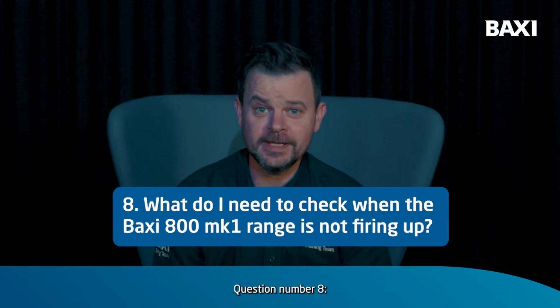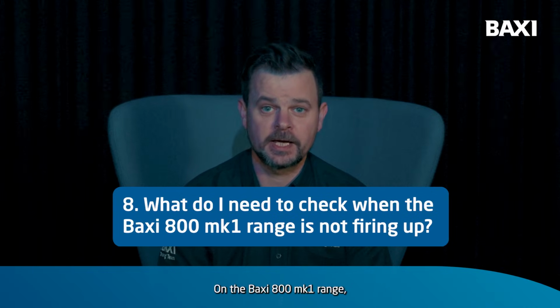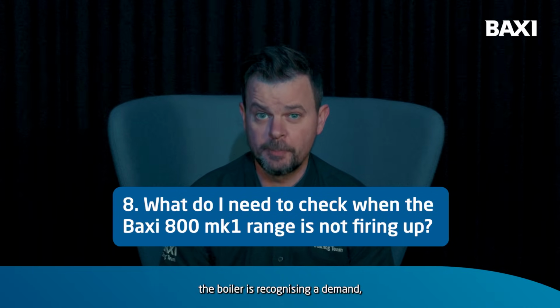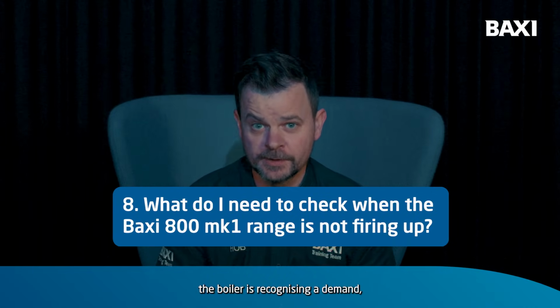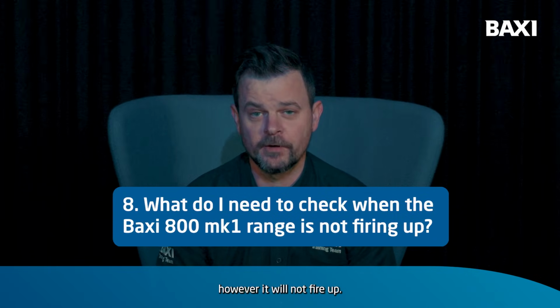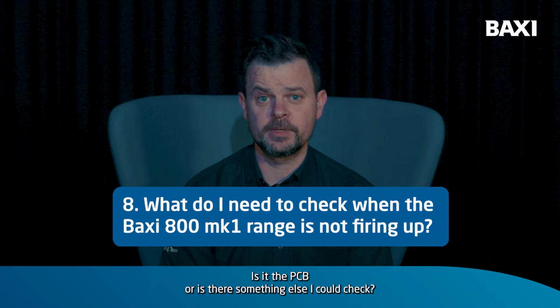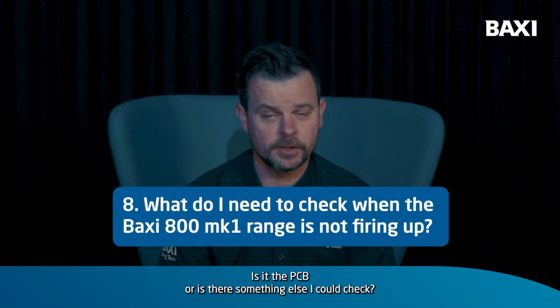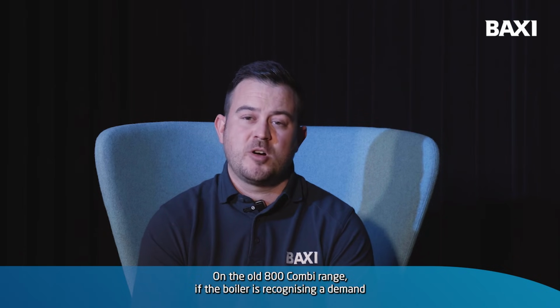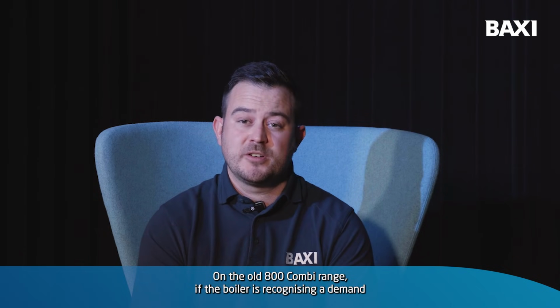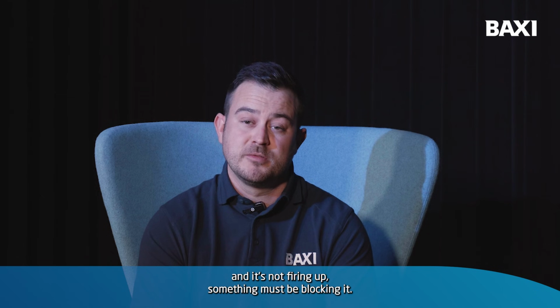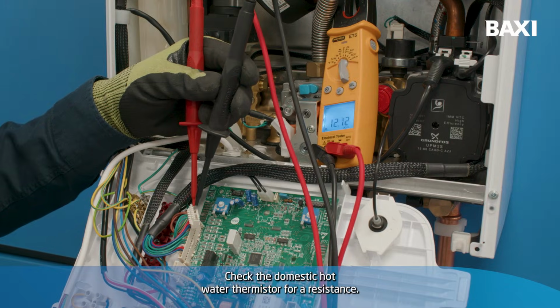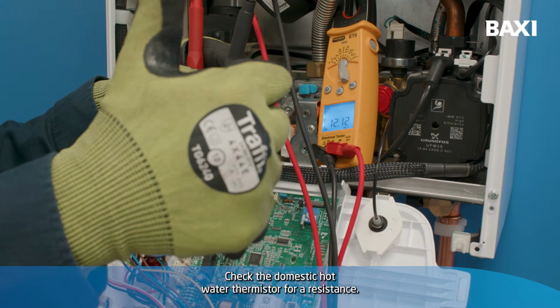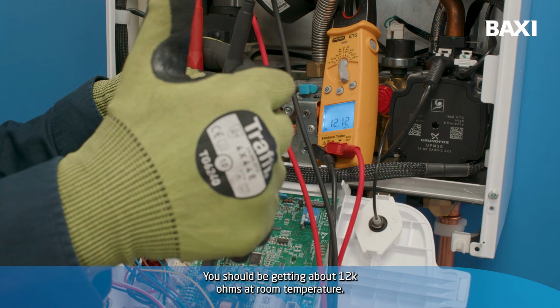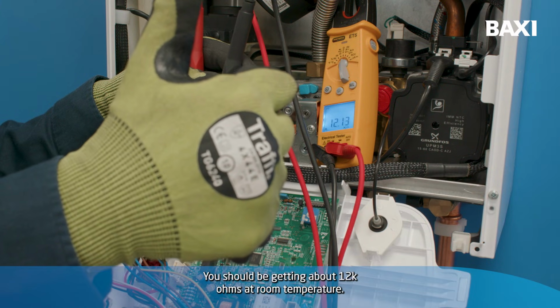Question number 8. On the Baxi 800 Mark I range, the boiler is recognising a demand. However, it will not fire up. Is it the PCB or is there something else that I could check? On the old 800 Combi range, if the boiler is recognising a demand and it's not firing up, something must be blocking it. Check the domestic hot water thermistor for resistance. You should be getting about 12 kiloohms at room temperature.